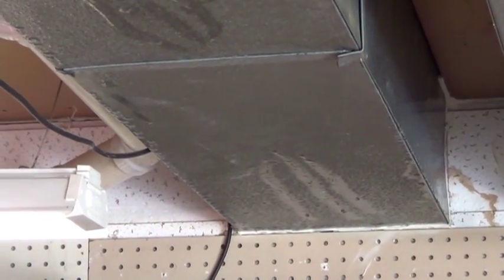So to avoid this, the next step we'll take after sealing the ducts is to make sure that they're well insulated. And we can do that with an insulation wrap, or a spray foam, or a combination of materials. But if you look all the way down, you can see these ducts are dripping. See the big droplets all the way down. So this is going to be something we want to avoid. And on the other side of the ducts, you can see this has been a historical problem because we've got rust forming. We've got some streaks here where water's been showing to rust.